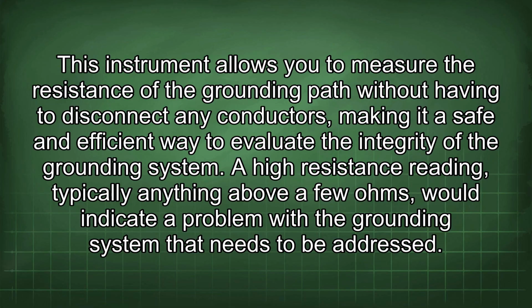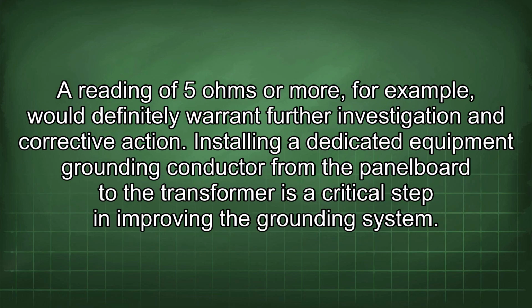A high resistance reading, typically anything above a few ohms, would indicate a problem with the grounding system that needs to be addressed. A reading of 5 ohms or more, for example, would definitely warrant further investigation and corrective action. Installing a dedicated equipment grounding conductor from the panel board to the transformer is a critical step in improving the grounding system.